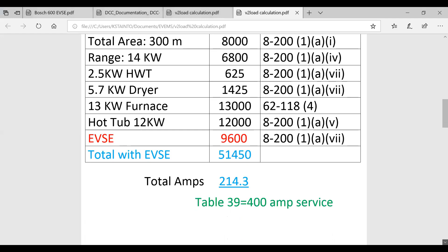I wanted to include the fail-safe value in there so you guys could see what to do if you have a fail-safe value that you have to calculate in. I do understand the CEC technically has a 0 amps for fail-safe, but I've included this here just so I can show you how to go about doing it.